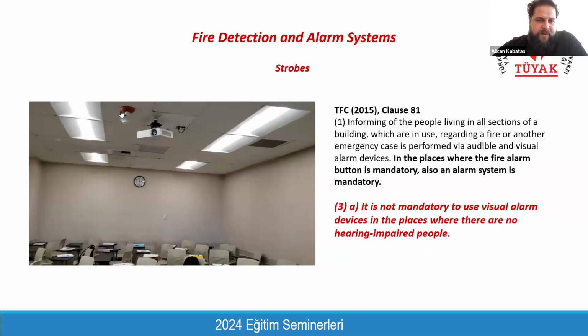And this is one of the examples of the strobe. It can be located either on the ceiling or on the wall, but you need to inform the electrical designer of your preference, locate your preferred location of the strobes, because the type which is used on the wall is not the same equipment that they are using on the ceiling. That's why at the beginning of the design phase, you need to inform electrical designers that architecturally strobes are required to be on the ceiling, or they are required to be located on the walls.